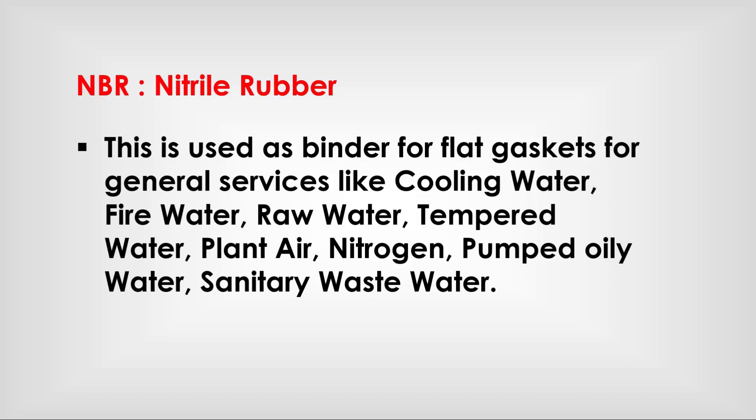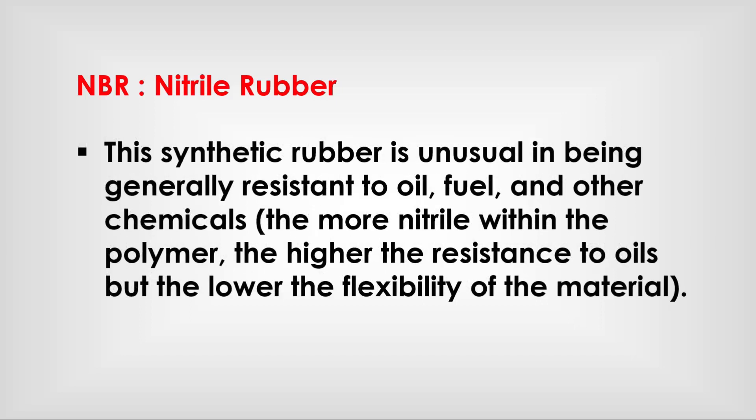NBR (Nitrile Rubber) is used as a binder for flat gaskets in general service such as cooling water, fire water, raw water, tempered water, plant air, nitrogen, pumped oily water, sanitary waste water. This synthetic rubber is generally resistant to oil, fuel, and other chemicals. The higher the nitrile content within the polymer, the higher the resistance to oil but the lower the flexibility.